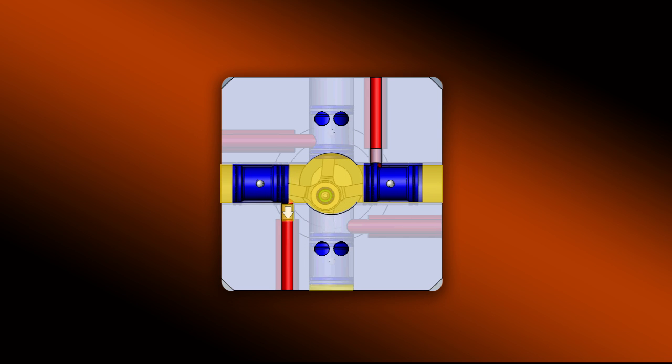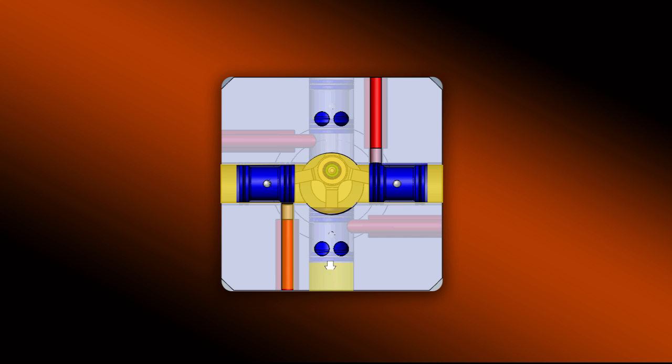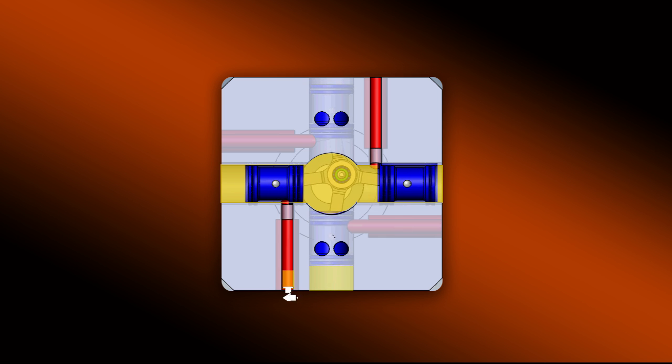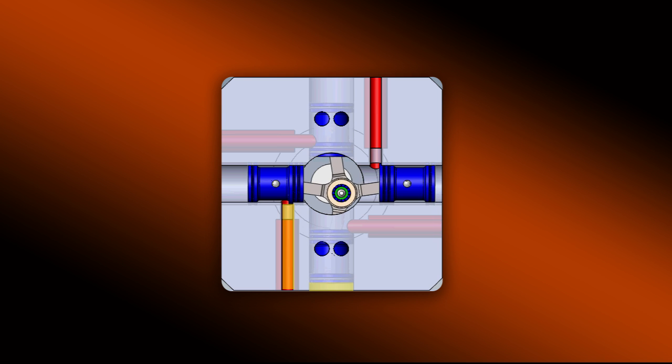The principles of the volumetric design are simple. Fluid enters the meter from a central cavity, then progresses through the meter, displacing an internal piston. Fluid then returns through the meter and is discharged through outlets located within the piston chamber.